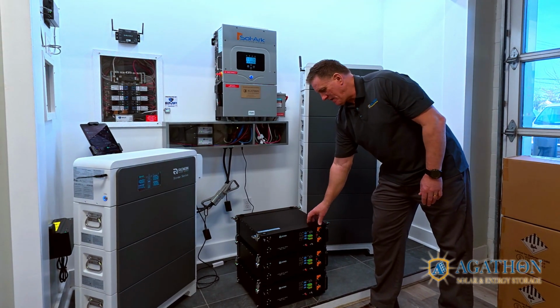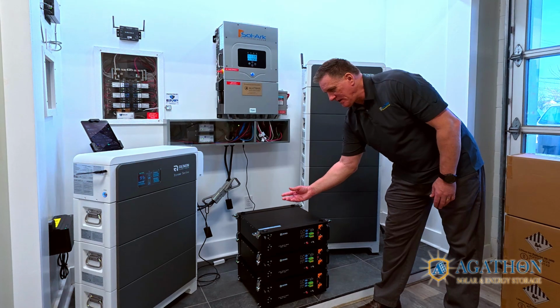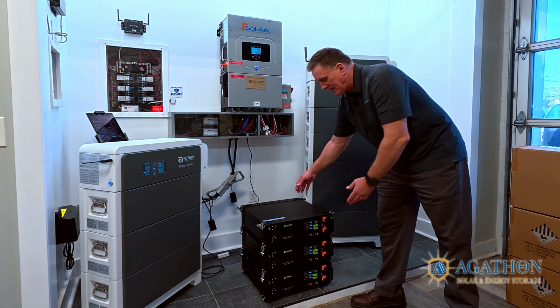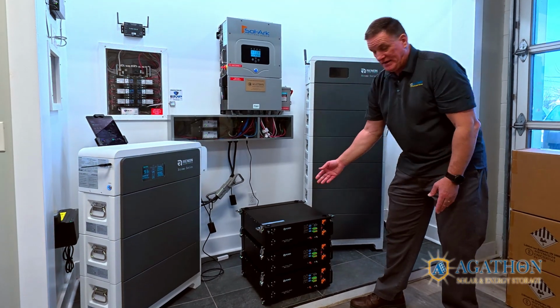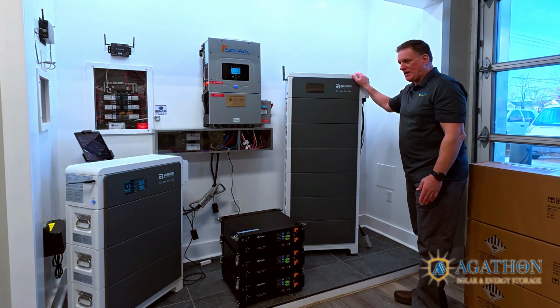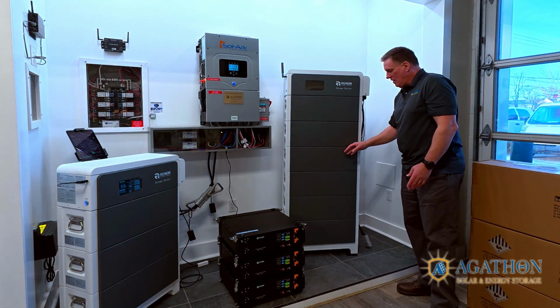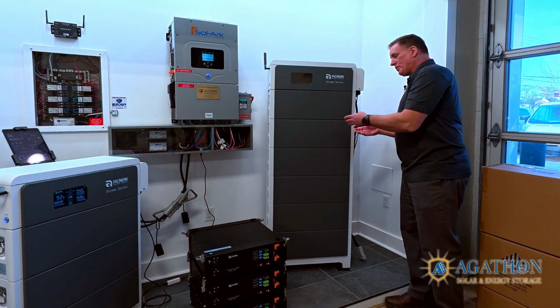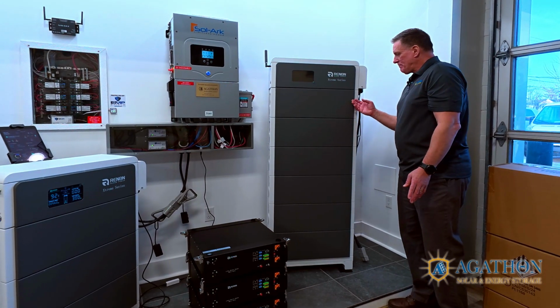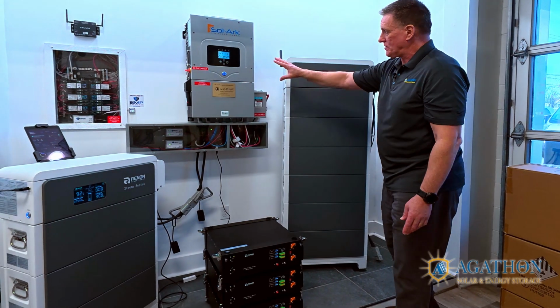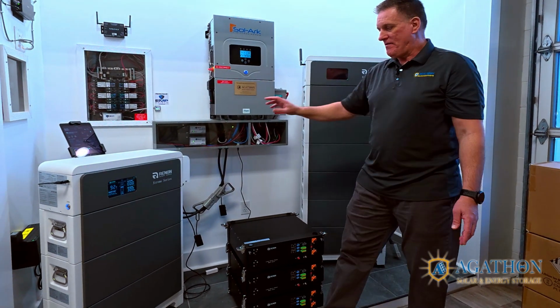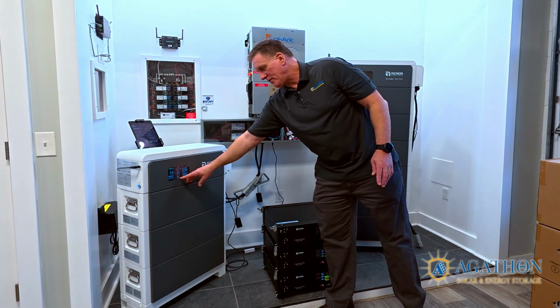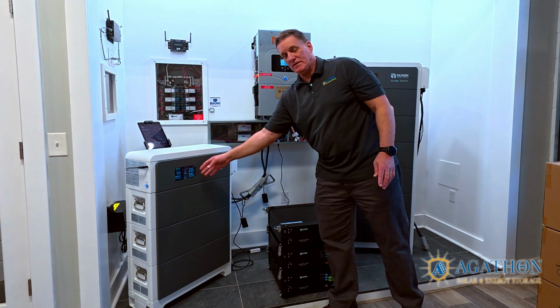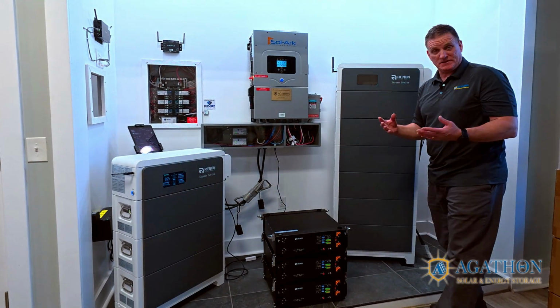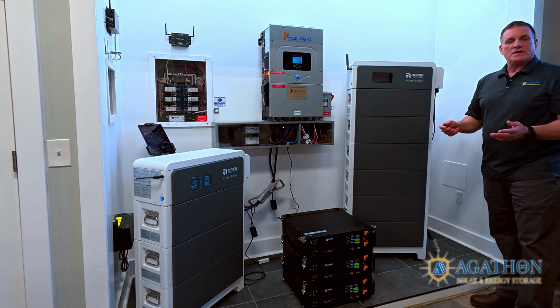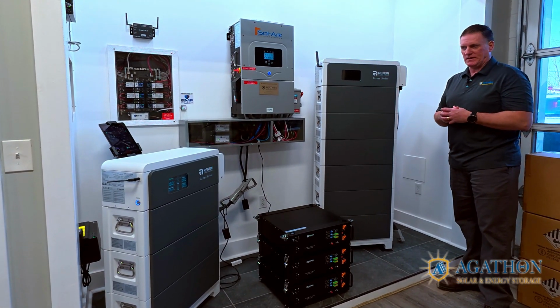This eBrick system has these racks that can easily expand the system, giving it stability and, again, the ease of expansion. One of the greatest features of the Renon is this stackable modularity. So you can add a battery or 2 or 3, and you simply change the settings in the Sol-Ark to recognize the increased capacity. And the Renon has an auto detect feature, so it will auto detect how many modules are in it. This is one feature that we really like about this battery as an installer, as opposed to some of the other batteries that do not have the auto detect feature.